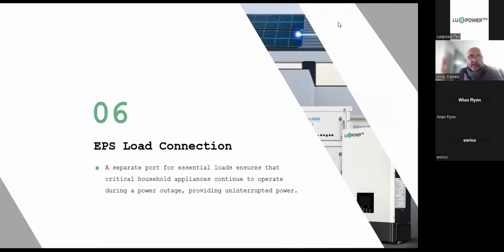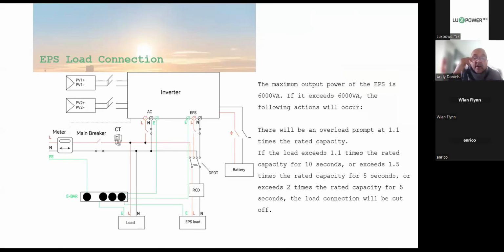On the EPS connection side, the load connection side, a separate port for essential loads ensures that critical household appliances continue to operate during a power outage. You guys know that. It's very common here in South Africa. Load shedding taught us that. And this is where the machine became very, very popular, the fact that it could operate either as a UPS or as a PV power supply. We've now included extra features on here, which I'm going to go through with you. But this is, once again, just a typical diagram of what the layout looks like.